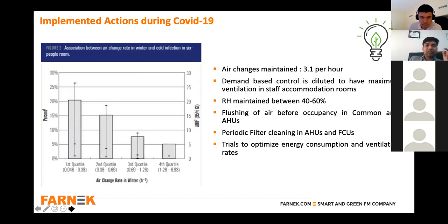The graph on the left-hand side, from the ASHRAE journal, shows a relationship between air changes and common cold infection in a dormitory. As air changes increase, infection rates drop. When air changes go above 1.3, the rate of infection for the common cold drops below 5%. Keeping this in mind, we are providing the maximum possible air changes to our facility, around 3.1 per hour from our existing system. We have removed the demand-based ventilation system for the staff accommodation so that we provide maximum fresh air supply to the rooms and dilute the contamination rates inside the facility.